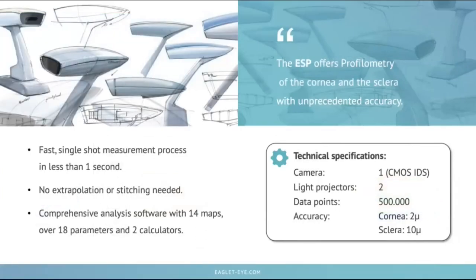This gives us a fast, single-shot measurement process that occurs in less than a second. We don't extrapolate the data and we don't stitch data together — it's real data. Included in the ESP is comprehensive analysis software with over 14 maps comprising 18 different parameters and two lens calculators. It's accurate on the cornea to 2 microns and the sclera to 10 microns, giving us unprecedented accuracy of both corneal topography and scleral profilometry.